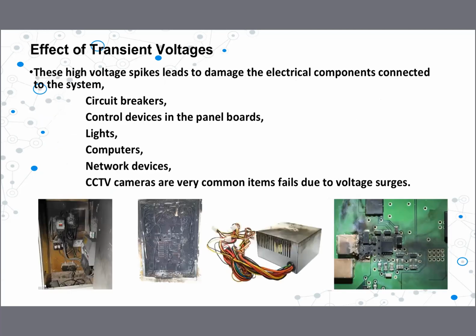Then let's try to understand the consequences, what the damages are, and what equipment can be damaged due to these voltage spikes. Circuit breakers in the electrical system can be damaged due to transient voltages or voltage spikes. Control devices in the panel board can easily be damaged due to these transient voltages. Then lights, especially nowadays as we are using LED lights, I think you would have experienced this very well: these LED lights are burned out, damaged due to this transient voltage. Then computers, especially network devices, network switches, and also very commonly CCTV equipment can be damaged.